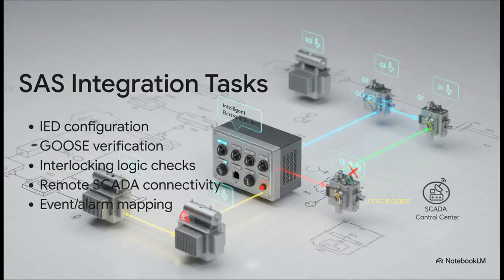This is where the real digital magic happens. Engineers test these critical signals called GOOSE messages. Think of them as urgent digital signals that fly across the network in just a few milliseconds to tell a circuit breaker to trip during a fault. They also test safety interlocks to prevent dangerous mistakes, confirm everything can be seen and controlled from the main control center, and map out every possible alarm.